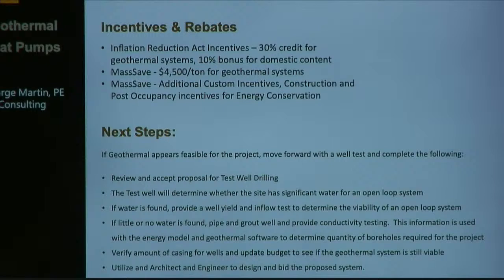You have controls to monitor this stuff, but we've seen that if you don't have heat exchangers at all—some systems are designed that way—it can foul the actual heat pump loop, which is not good. We separate that hydraulic loop with a heat exchanger. So there is a little more maintenance, but the design inherently limits that issue. However, you do have potential for more operational costs if it's not designed right—for instance, more pressure needed to inject into the ground can mean more costs on the open loop side versus closed loop. These are design decisions we consider carefully to ensure robust systems. We won't give you a system that's hard to maintain, but there are things to consider.